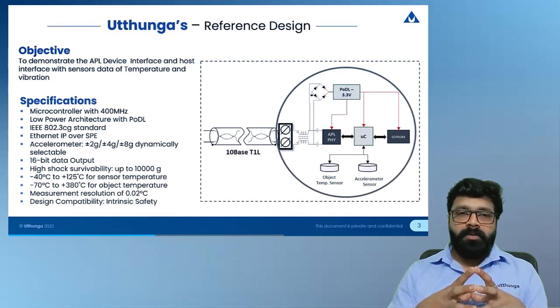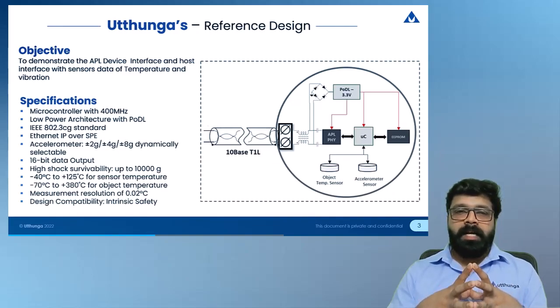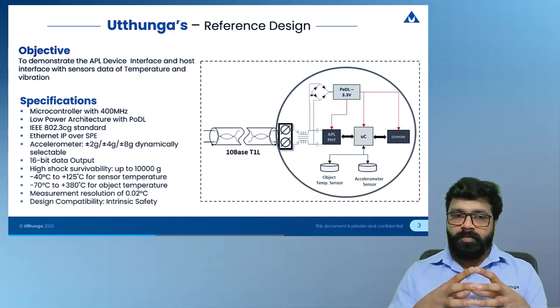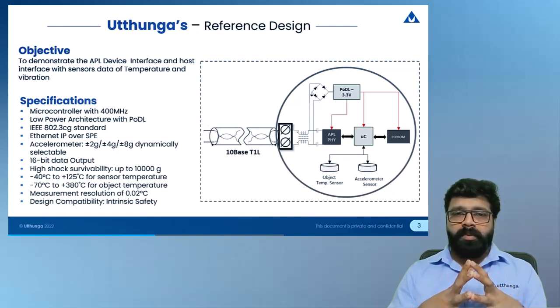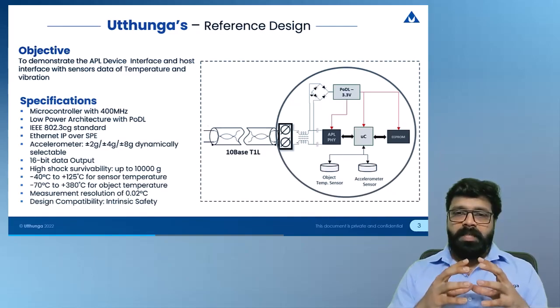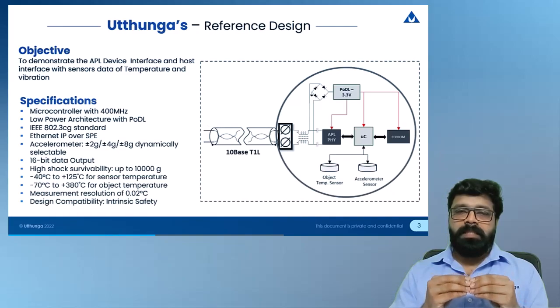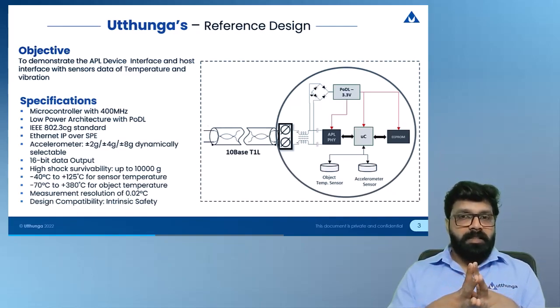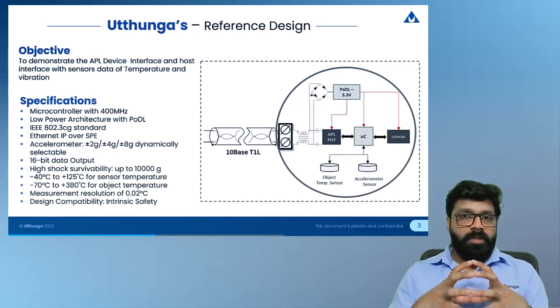The design is compatible with the IEEE 802.3cg standard, which is the SPE specification. It comes with an accelerometer having up to ±8G dynamically selectable range, 16-bit data output, and high shock stability. Temperature compatibility ranges from -40°C to +125°C, with an object temperature sensor measuring from -70°C to +380°C, measurement resolution up to 0.02°C, and intrinsic safety compatibility allowing deployment in Zone 0.